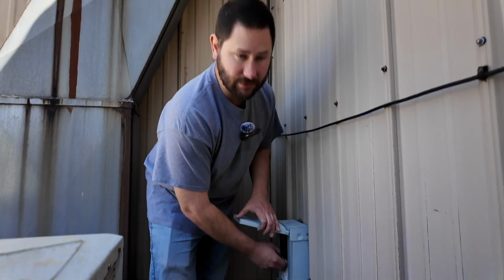We're going to use our drill, our 5/16, to take apart this package air conditioning system. We're going to be cleaning the indoor coil and the outdoor coil. They need to be cleaned every year because they can get really dirty. Before you clean any air conditioner or perform any maintenance, make sure that you disconnect the power.